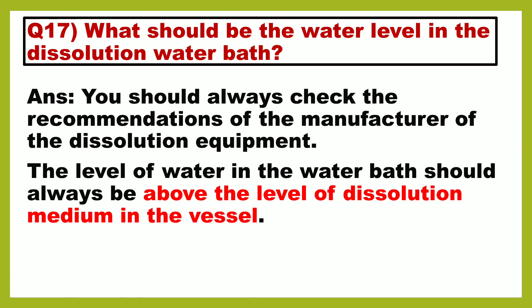Next question is: what should be the water level in the dissolution water bath? You should always check the recommendation of the manufacturer of the dissolution equipment. The level of water in the water bath should always be above the level of the dissolution medium in the vessel.